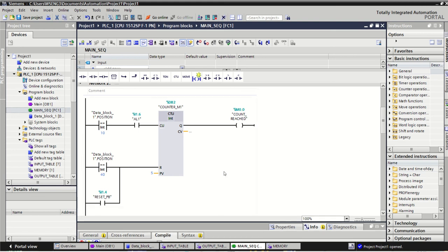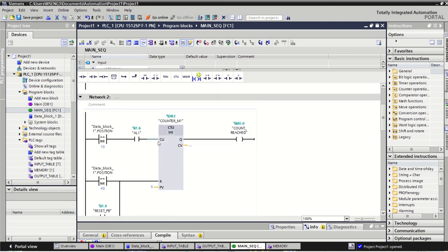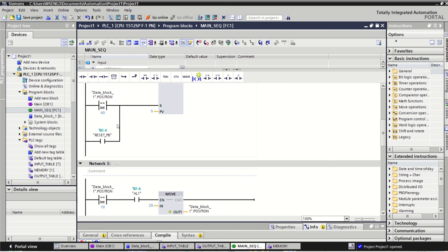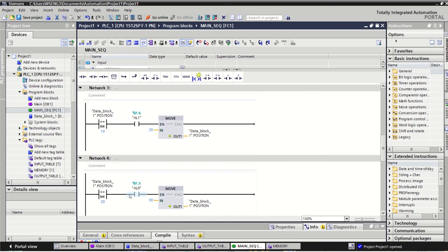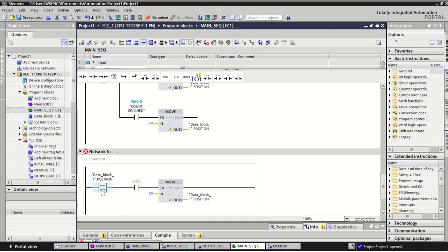And that essentially would be all the code that you would need for that. You're just starting your sequence, you've put in your counter, making sure you use your counter bit. You reset in an automatic way and a manual way, you're using the integer to only count this input at this moment in time, at this step number. You have the pairing that will go through, and then you have the query to say, has the count been reached? No, okay, go back and do it again. If it has, continue on down the line and reset your counter.